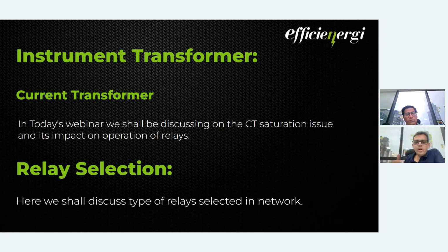And the second part of the webinar, so that will be the first part which we'll be focusing on. In instrument transformers, we are not going to be covering other transformers. We realized that covering just CT, doing justice to CT saturation and its impacts on protective relay coordination or protective device coordination in itself is a very critical subject, and will require a certain amount of deep dive.